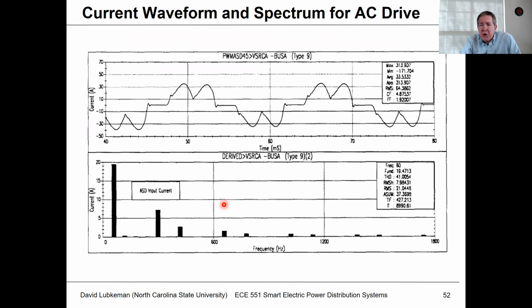And if you would look at this type of device in the field, here's another measurement where we're measuring the input waveform. You can see you've got these two spikes on the positive part of the waveform and two negative spikes on the second half. Then these power quality measuring devices, once they capture the waveform, you can do a Fourier analysis, and this shows the corresponding harmonic content.